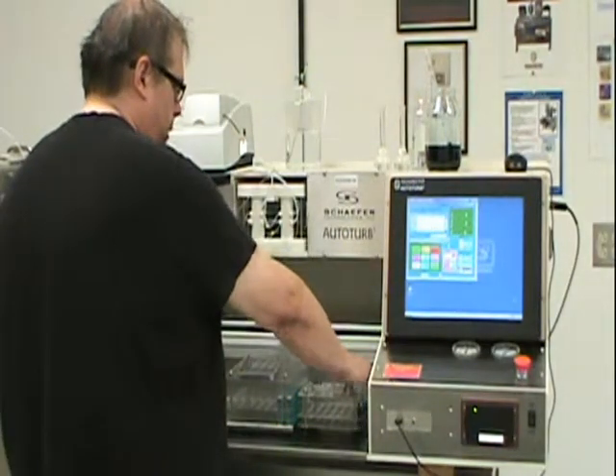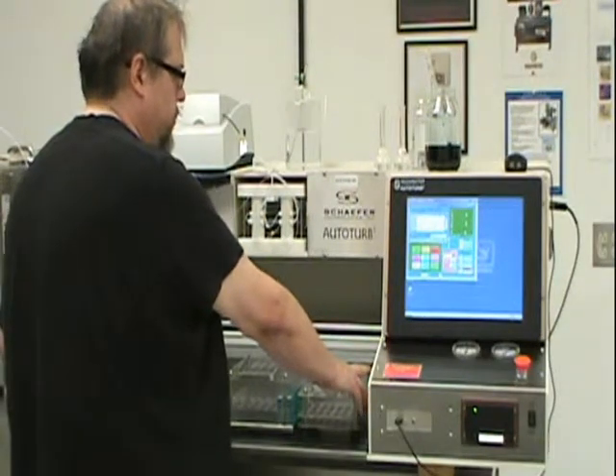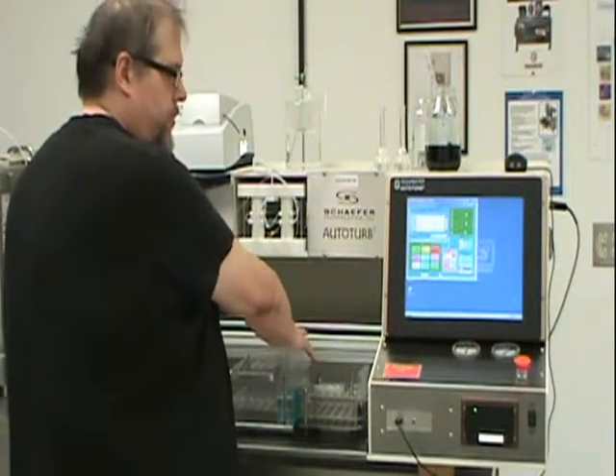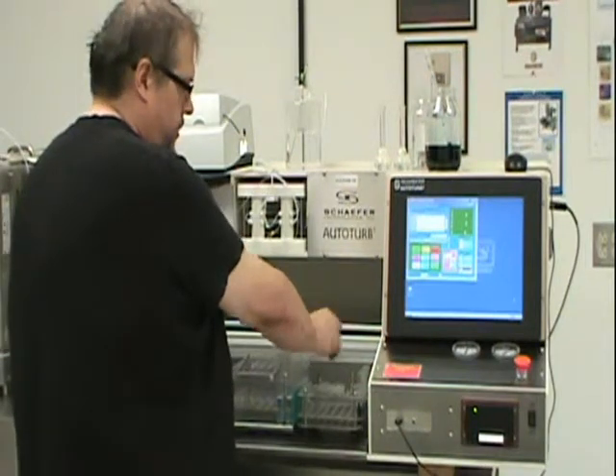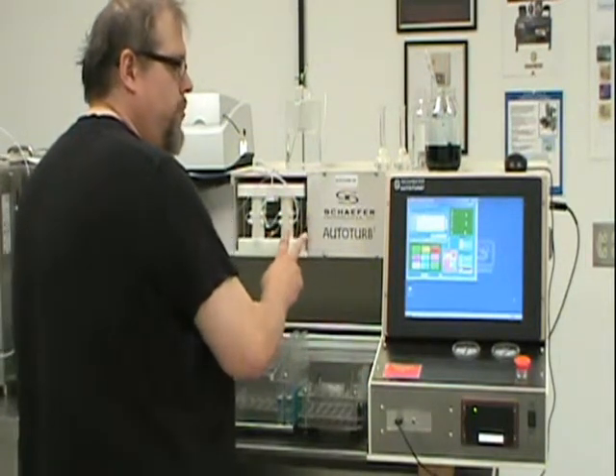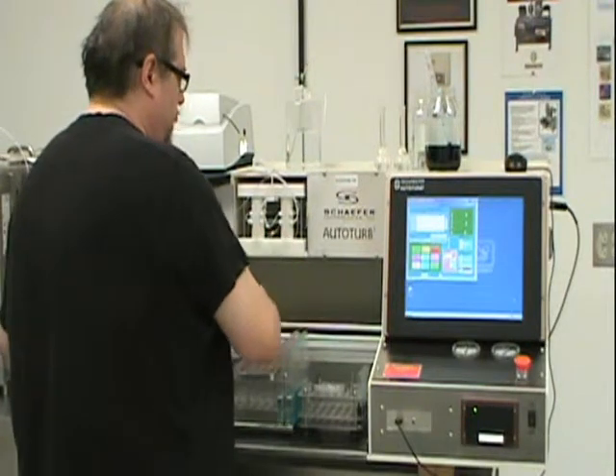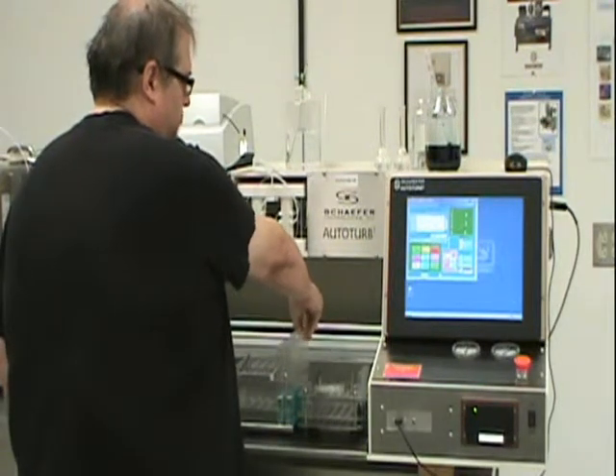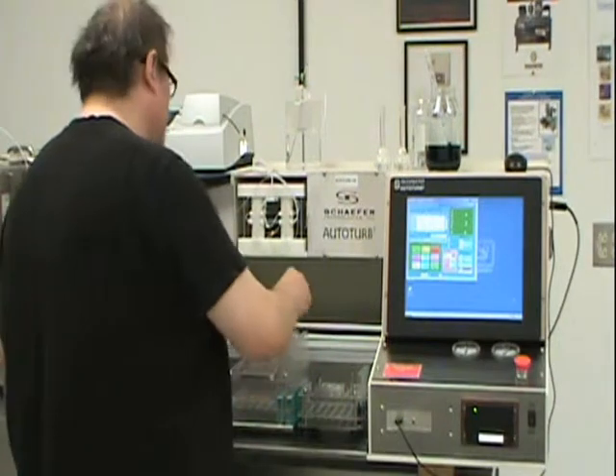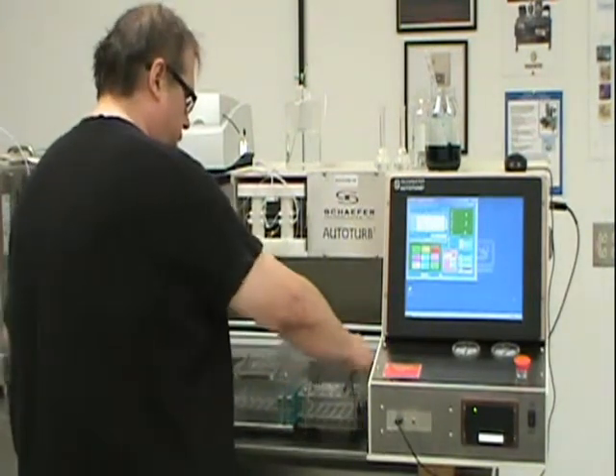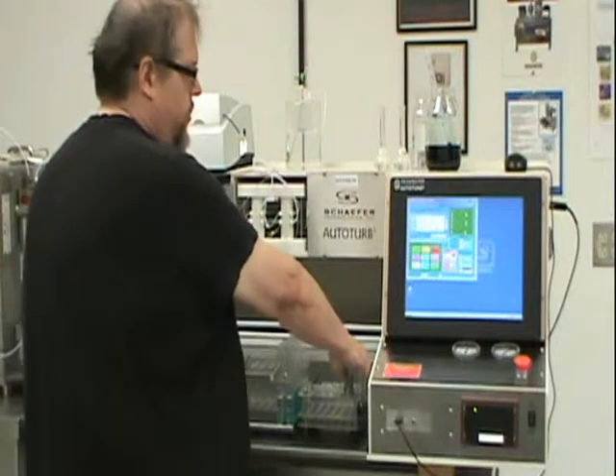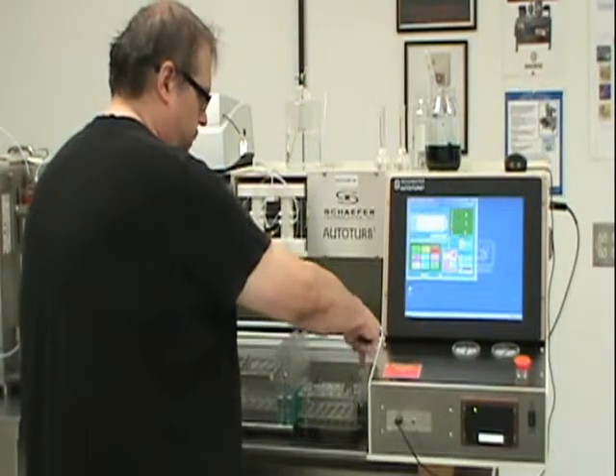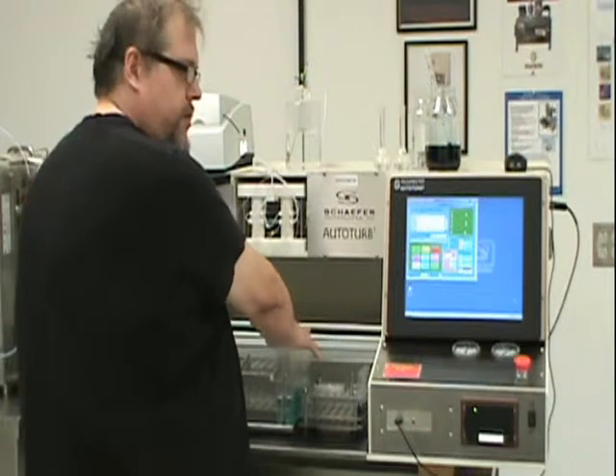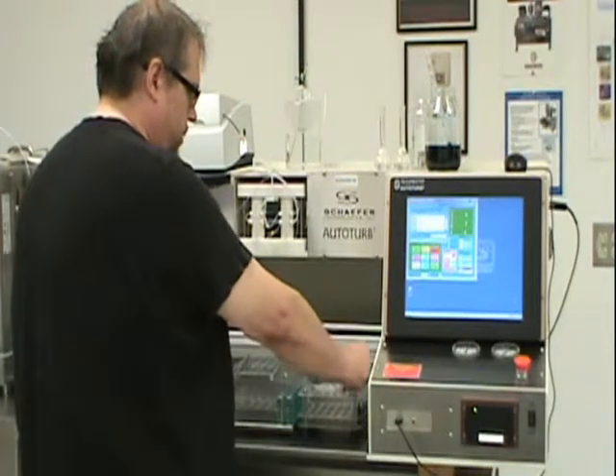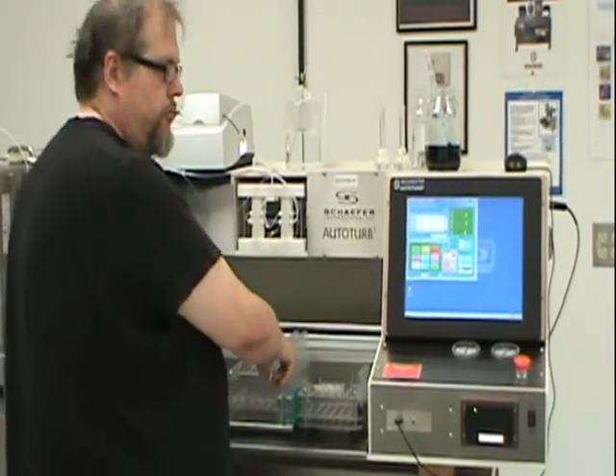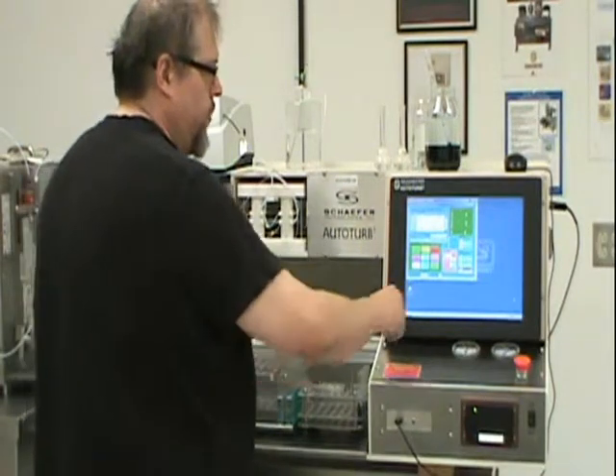So it's going to draw fluid from all 5 of these tubes, but it's not going to dispense all of the fluid that it draws from these tubes in this rack. The first tube is only going to do 2 samples instead of 4. The first two samples are going to be a waste. They're just going to be straight medium. And then the other half of the first tube is going to get lost in this case. Tubes 2, 3, 4 will dispense 4 each, just like before. The 5th one will only dispense 2 of its 4 loops. The other 2 will get lost into the waste pan.